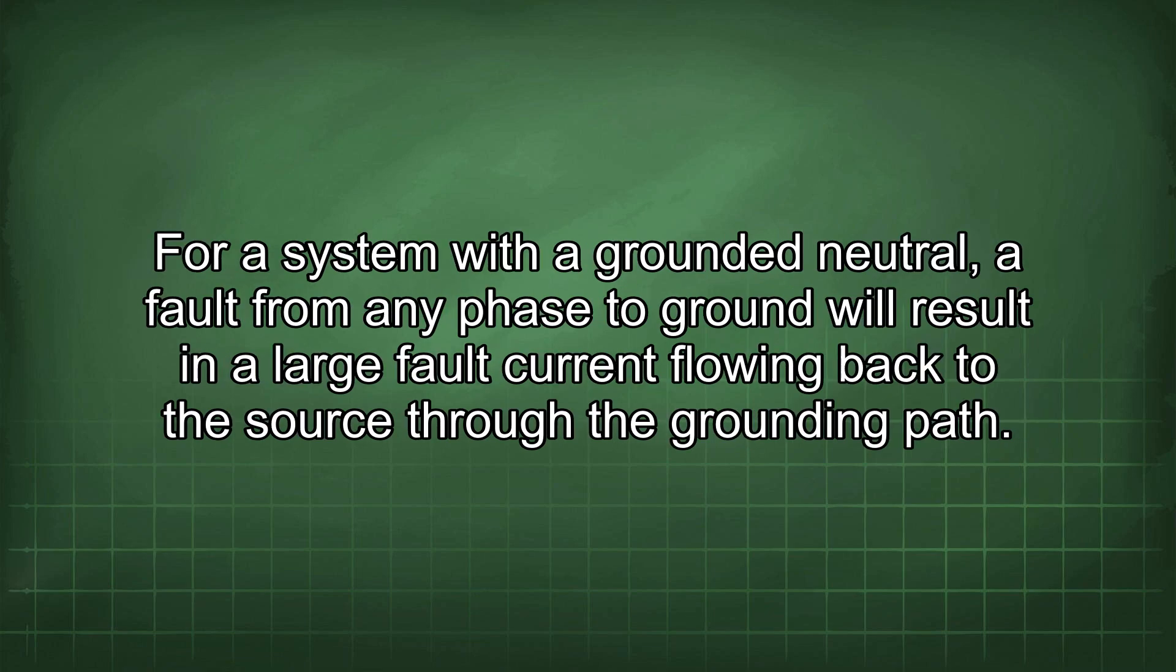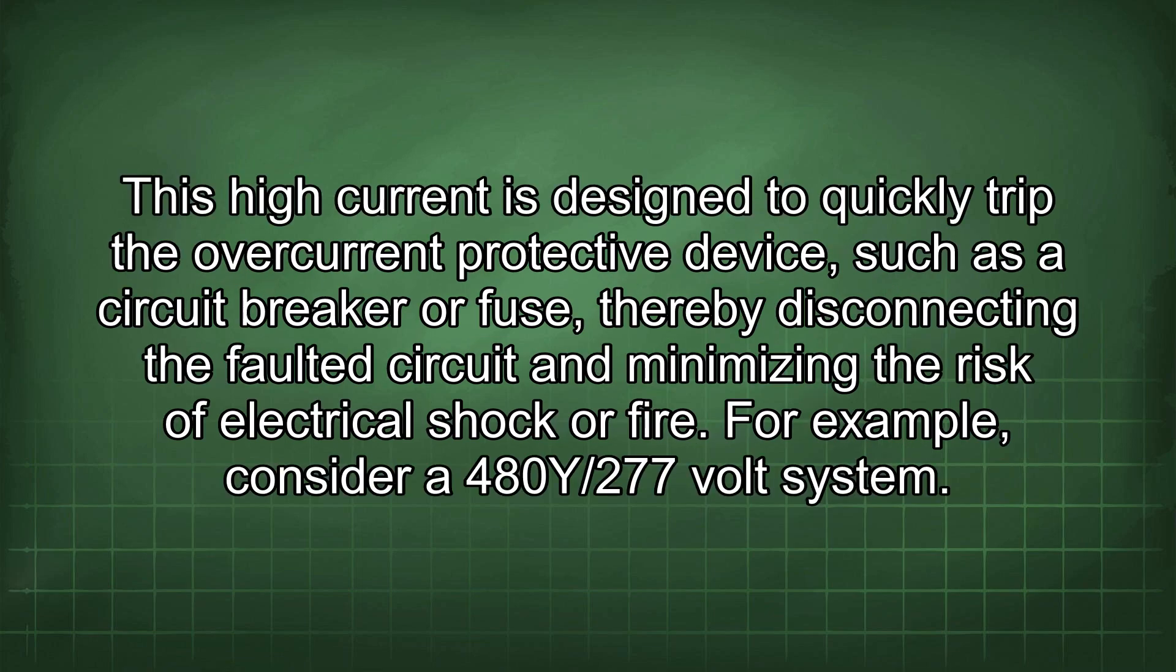For a system with a grounded neutral, a fault from any phase to ground will result in a large fault current flowing back to the source through the grounding path. This high current is designed to quickly trip the overcurrent protective device, such as a circuit breaker or fuse, thereby disconnecting the faulted circuit and minimizing the risk of electrical shock or fire.